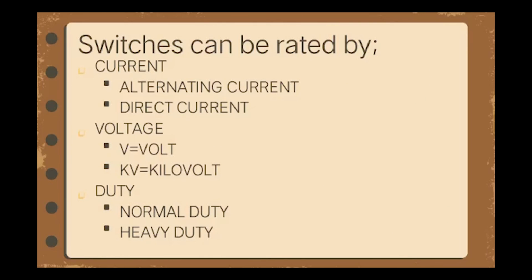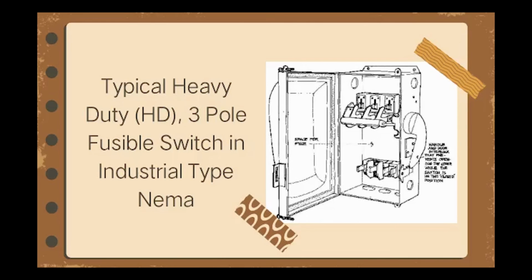Switches can be rated by current, alternating current and direct current, voltage, volt and kilovolt, duty, normal duty, and heavy duty. Pole and throw. Pole indicates the number of circuits that one switch can control, while throw indicates the number of contact points. Enclosure: cabinet for electrical equipment to mount switches to prevent electrical shock. And fusibility is the capability of being fused or melted by heating. This is the heavy duty or the HD. Triple fusible switch in an industrial type NEMA.